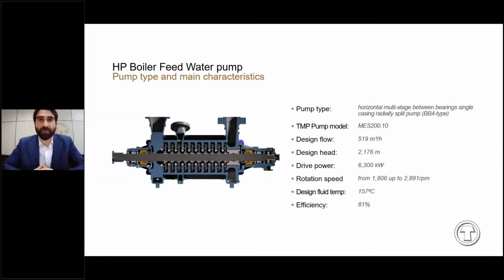Now I will give you some information related to the pump that we are going to test today. This is one of the various types of pumps that TMP can supply for the boiler feed application. It has been developed to fulfill all the performances requested by combined cycle plants using the new Class H gas turbine. This type of pump is a horizontal multi-stage, between bearing, radially split, and single casing, so without external barrel. That means its name is BB4 according to API 610 nomenclature.